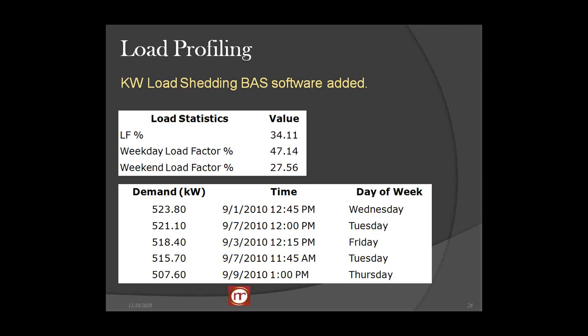Our biggest challenge will be January and February because this is a heat pump with electric strips. But we're expecting to load shed 150, 200 kW if we manage it correctly. And one of the things that needs to be understood is, remember rule number 1, improve the comfort level. Well, they do not need to know you're doing this. This is not cutting the equipment off. This is load shedding. If you do it correctly, nobody ever knows that you're doing it, and you have saved a ton of money in the process.